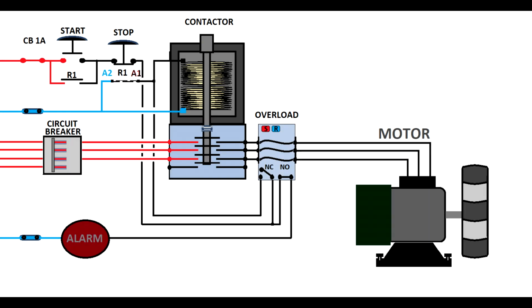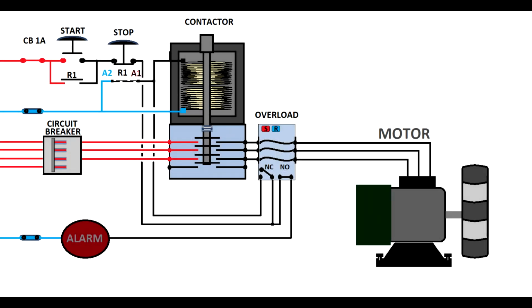Now the threshold has been breached and the overload interrupted the circuit. This is to protect the motor. So now you have to do an investigation before resetting the overload. The motor overload protection tripped and cut the power supply, but the alarm light for the ventilation system didn't turn on. You'll see here, it didn't turn on. But when you press the start, then the alarm will turn on, telling you that there's an alarm.